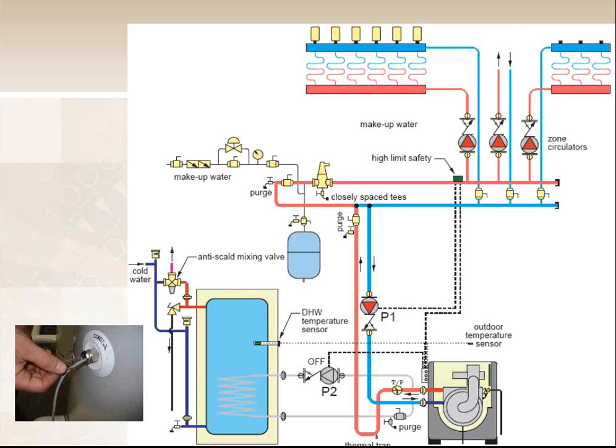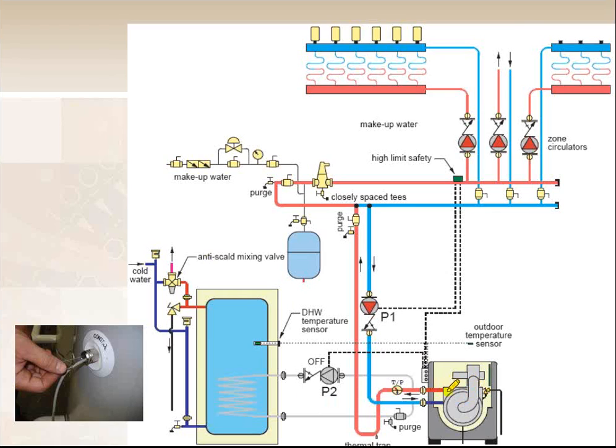So let's see if I can highlight it here. So down here at the bottom is my boiler, right? So his primary piping is this red line that comes out of here. My primary loop goes through my pump number 1 and back to the boiler, right? So that pump number 1, P1, his job in life is just to circulate water around this loop all day long. He doesn't care about anything else. That's all he does. That's his job.